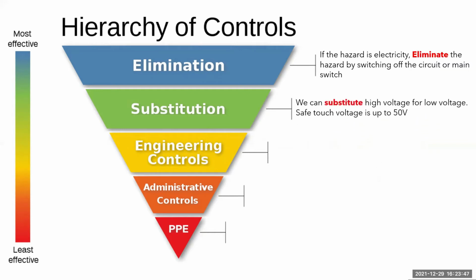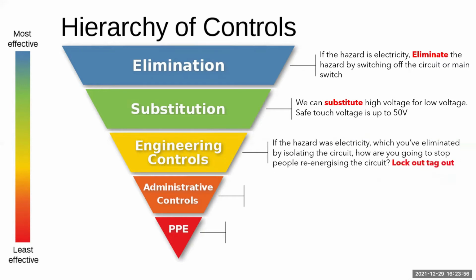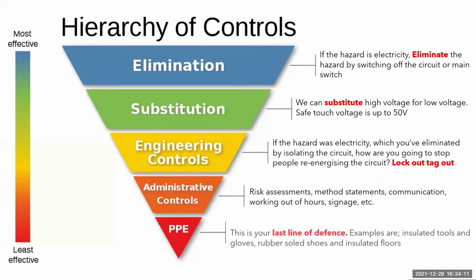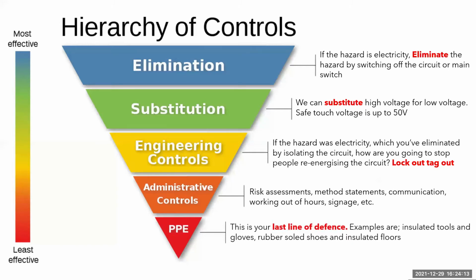We can substitute high voltage for low voltage, and 50 volts is considered to be your safe touch voltage, which we have discussed. Engineering controls are implemented to stop people interfering with your safe isolation process, and the admin controls are RAMs, signage, notifying people of procedures, working out of hours, and ultimately who is taking responsibility. Finally, we have PPE, which again is your last line of defense when all the other controls have failed, or as a way to lower any remaining risk after a risk assessment has been carried out.